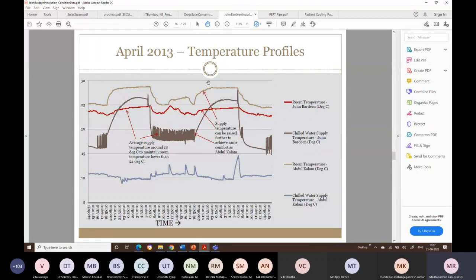This is data from one of the videos I showed, the Tech Mahindra one, where we measured and compared it to another block using an air handling unit. The top graph is the temperature in the area block using the air handling unit - that's the DBT. The red graph is the temperature of the space using radiant cooling. The third graph line is the temperature of the supply water to the radiant cooling system, and the bottommost one is the supply temperature to the AHU.